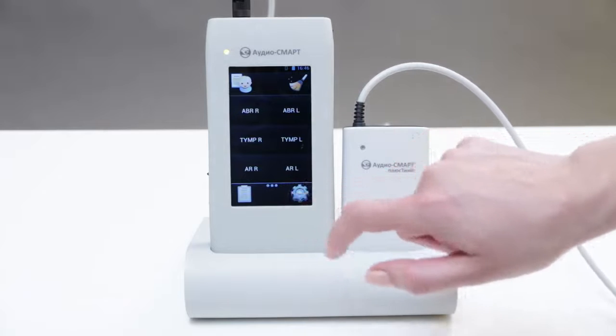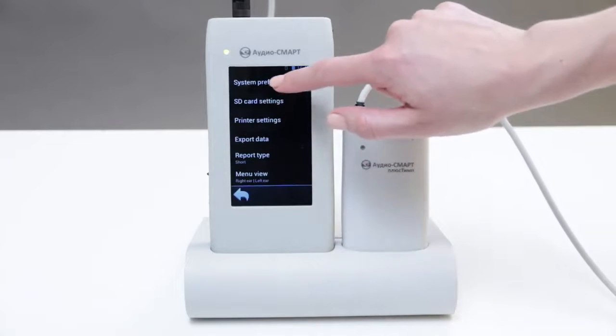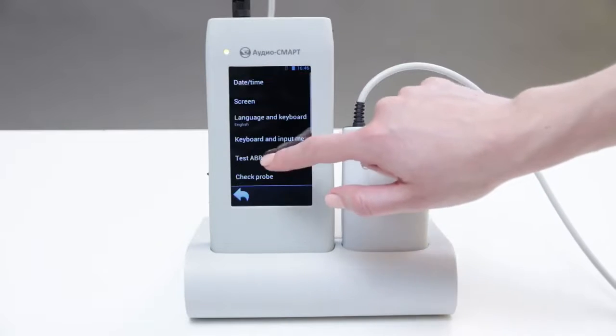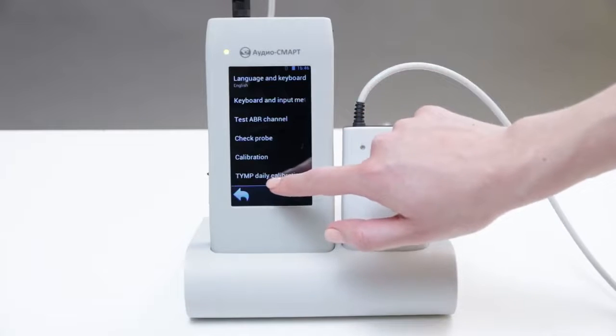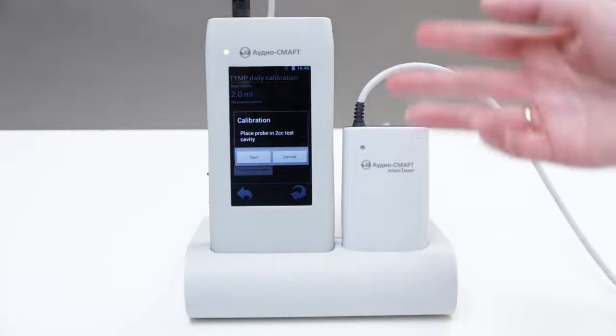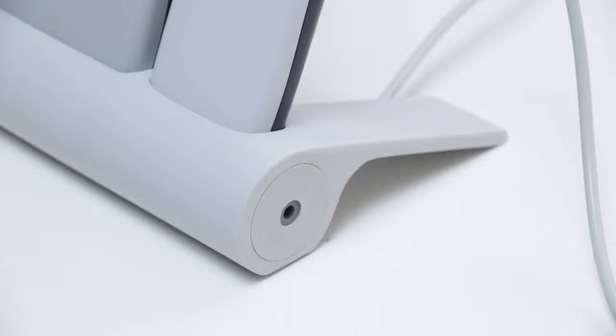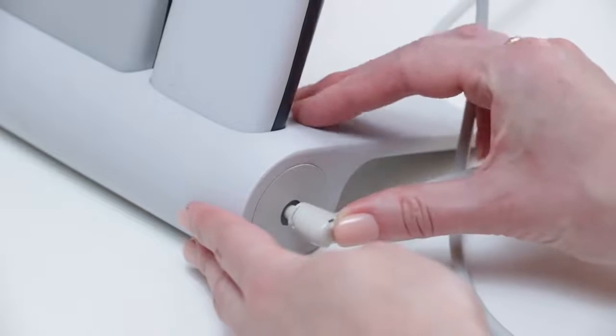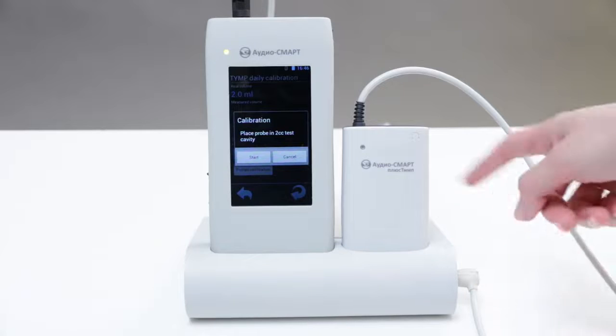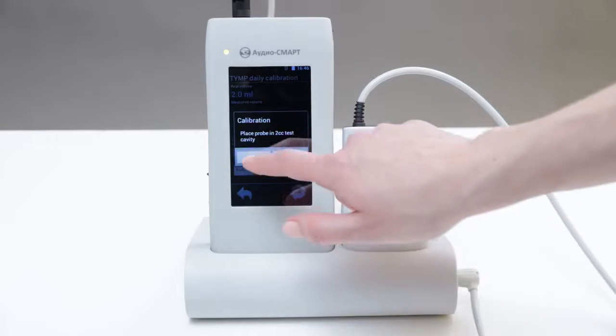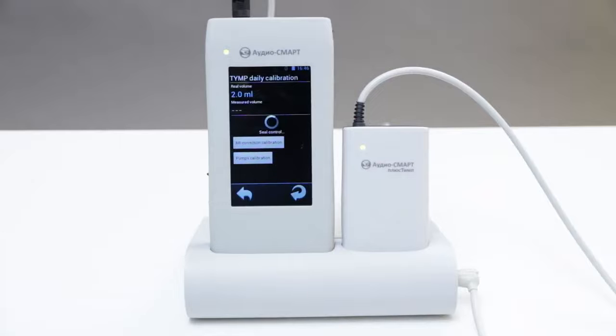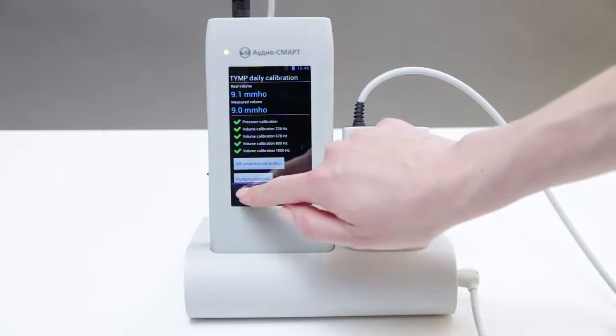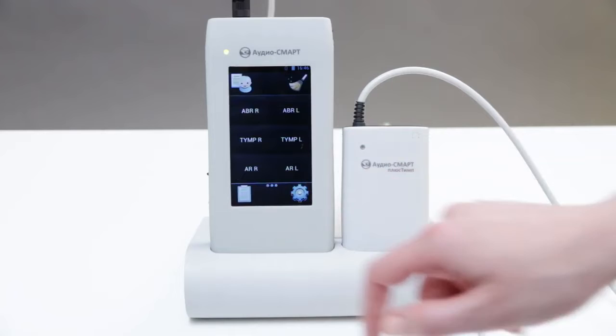We go to the setup, system preferences, TYMP daily calibration. Device asks us to position the probe into the testing cavity, test cavity inserting in the holder, and press start. The calibration has successfully finished, and we go to the main menu.